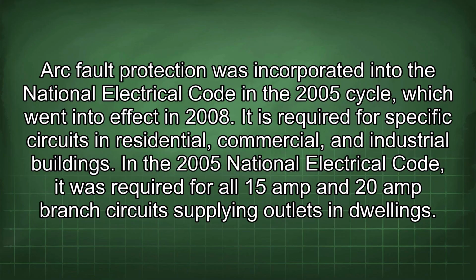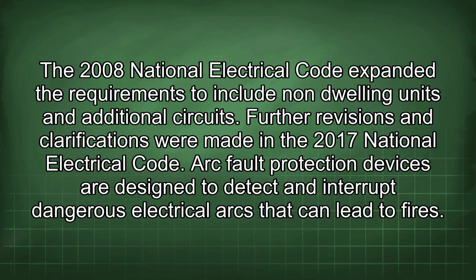Arc fault protection was incorporated into the National Electrical Code in the 2005 cycle, which went into effect in 2008. It is required for specific circuits in residential, commercial, and industrial buildings. In the 2005 National Electrical Code, it was required for all 15 amp and 20 amp branch circuits supplying outlets in dwellings. The 2008 National Electrical Code expanded the requirements to include non-dwelling units and additional circuits.